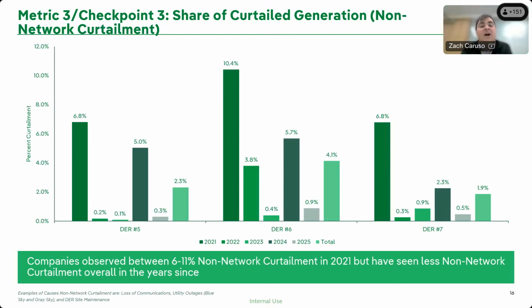And in addition to that, we have to look at the total amount of curtailed generation that we see, because one of the big takeaways we had from the project was that when you set up a control system that's monitoring these PV sites and the substation, if you lose communication to any piece in that control algorithm, in that control scheme, you have to take fail-safe action to reduce the power output of the PV sites to protect the system. Because as things are set up today, and Leo's going to go into a little more detail on this, we don't know when we're going into fail-safe, what time of year that is, or what else is going to be happening on the circuit.